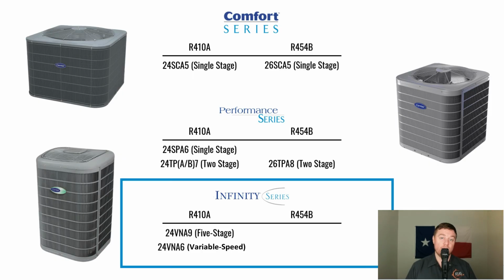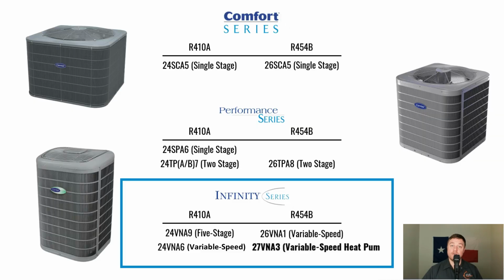And lastly, we have Carrier's Infinity Systems, which is the highest tier equipment that they offer, and is fully communicating. And this is where we see a major product shakeup. So the old Infinity products were a 24VNA9, which is their 5-stage communicating condenser. So the product that's replacing their 5-stage condenser is a 26VNA1 and is fully variable speed. So they're getting rid of the 5-stage line altogether and going fully variable speed. And the 24VNA6 was their Greenspeed model that is fully variable speed. They're wanting you to use a 27VNA3, which is a heat pump. So the product lines for Carrier's Infinity Systems have completely changed.